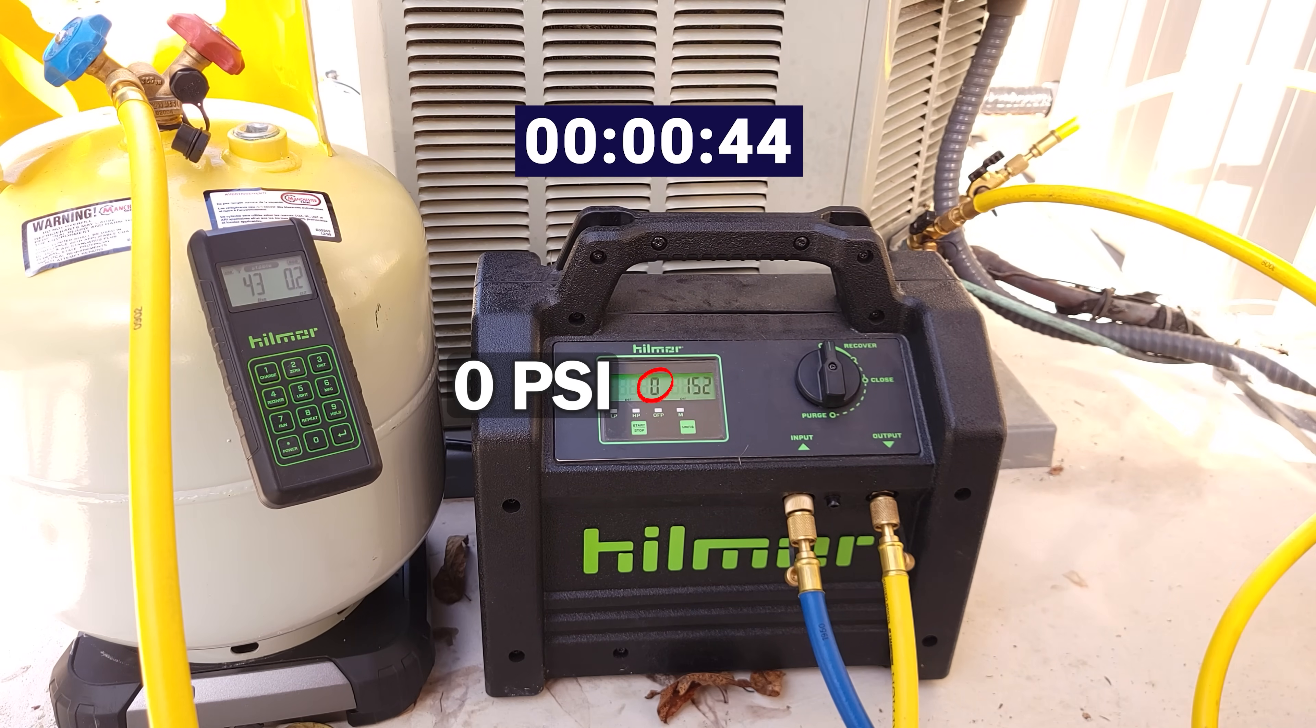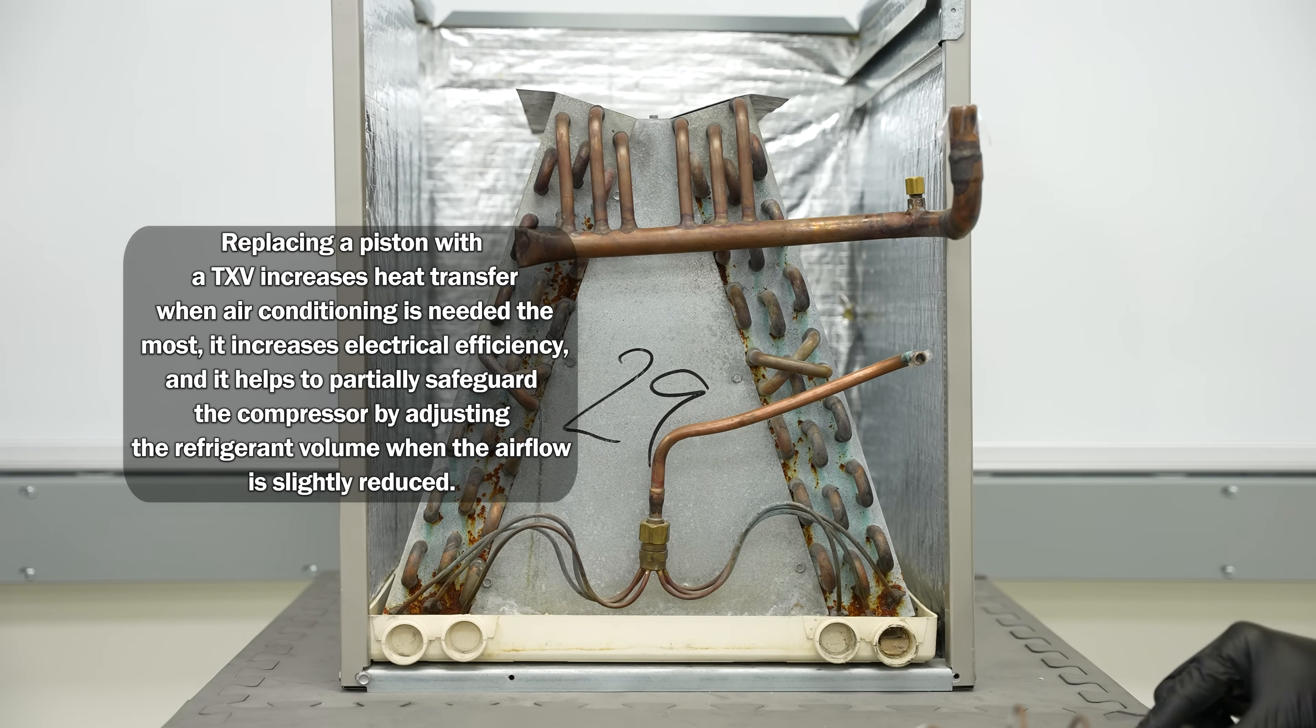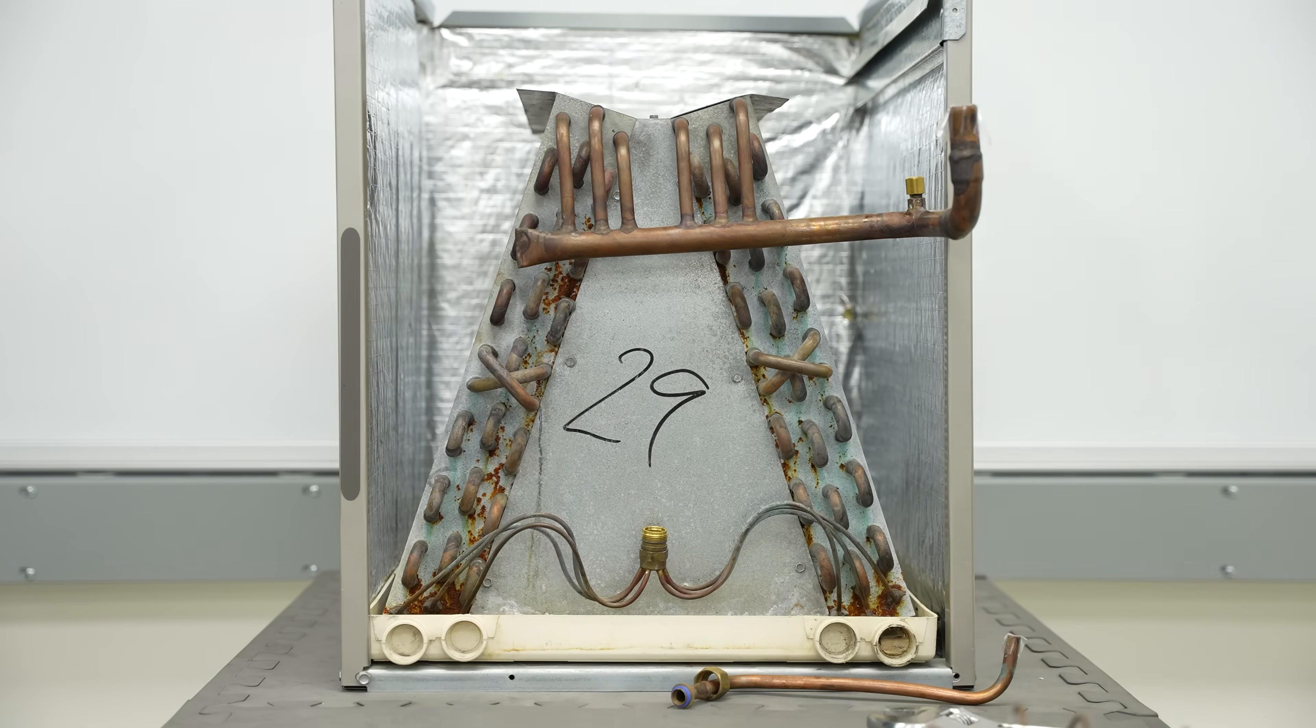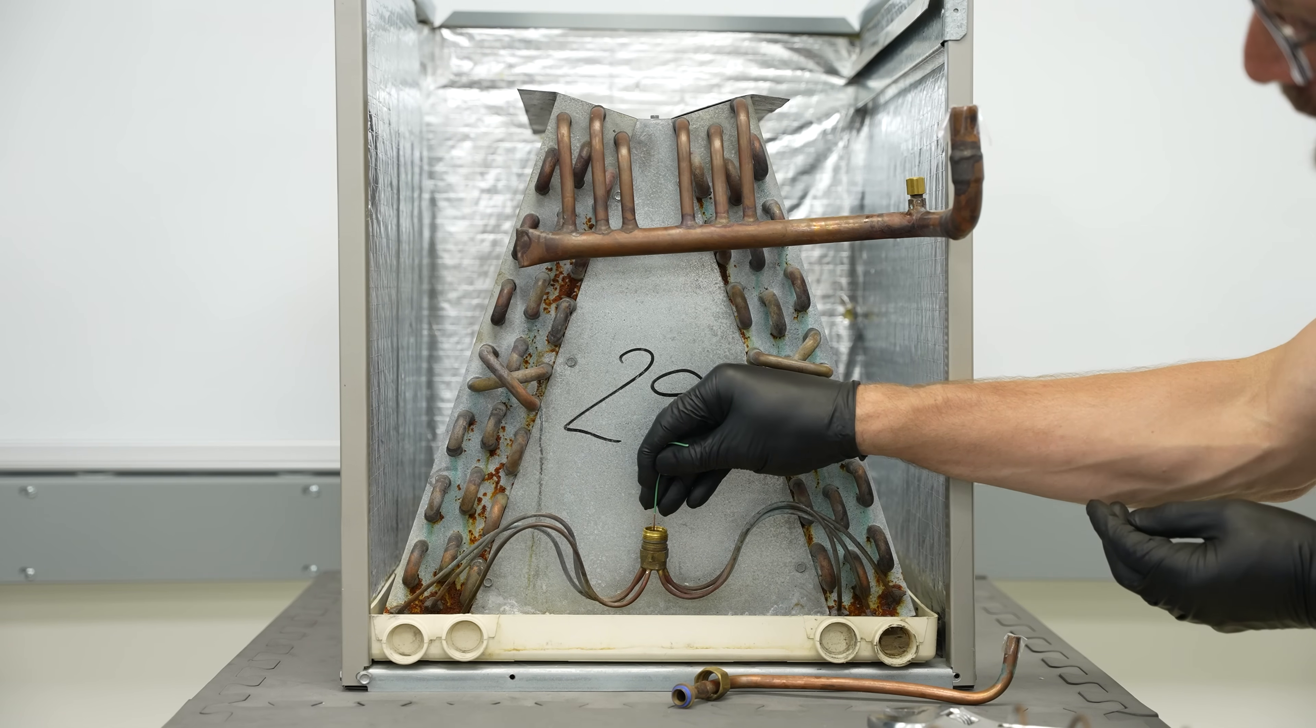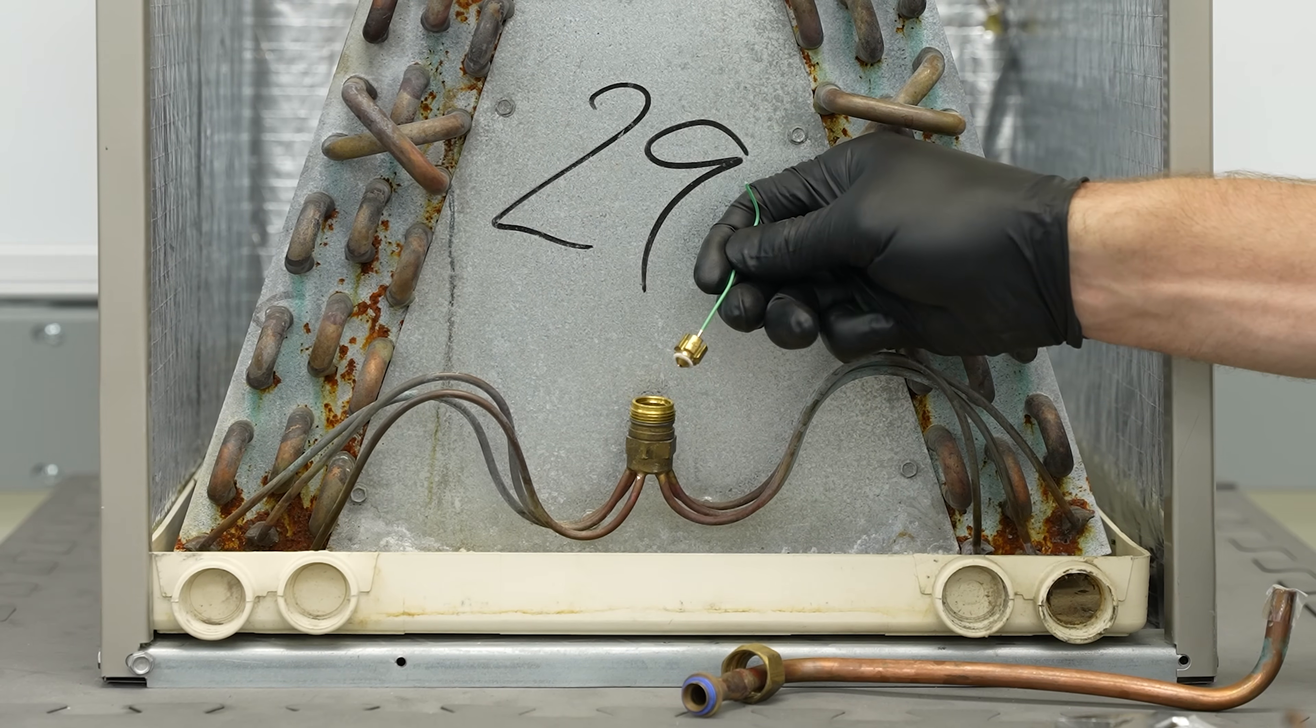After you've recovered the refrigerant down to zero PSI, you can go ahead and disconnect your piston chamber and pull out the piston. Then you can take a piece of thermostat wire with a little bent end on the edge and just pull out the piston. Remove this cap.